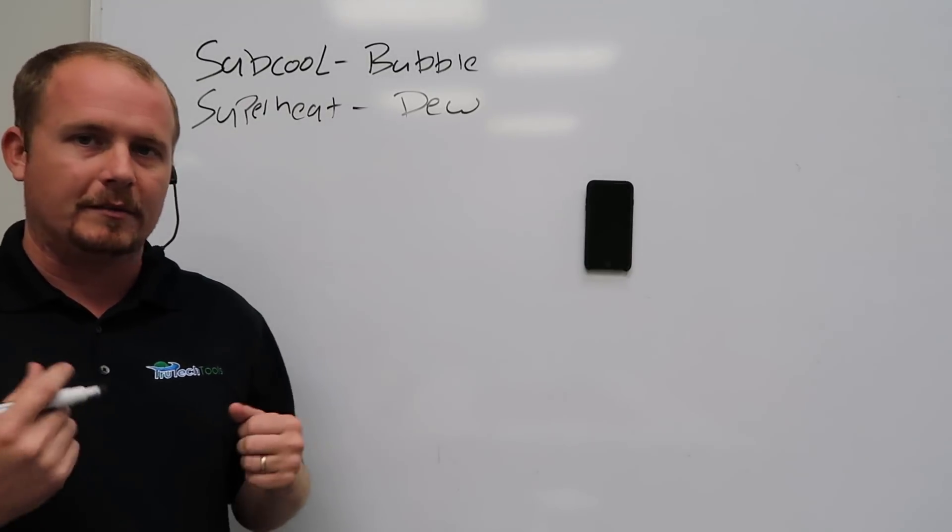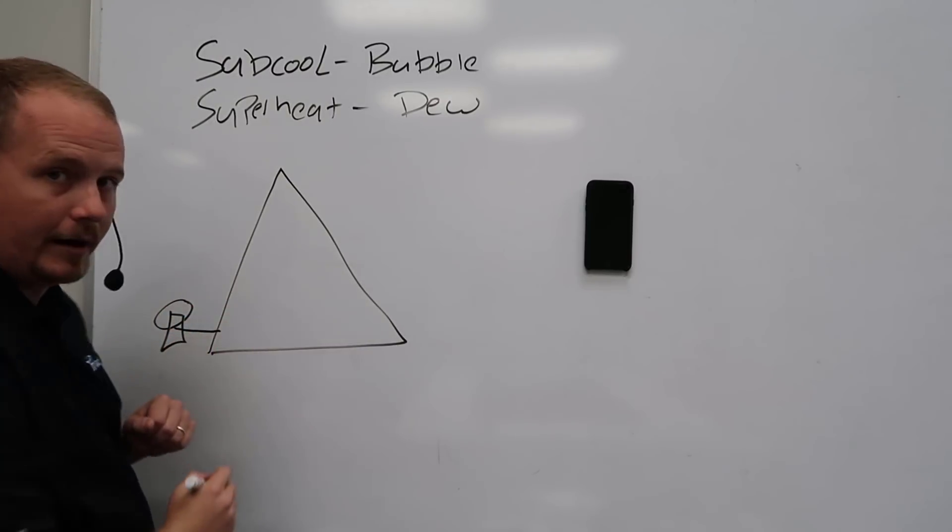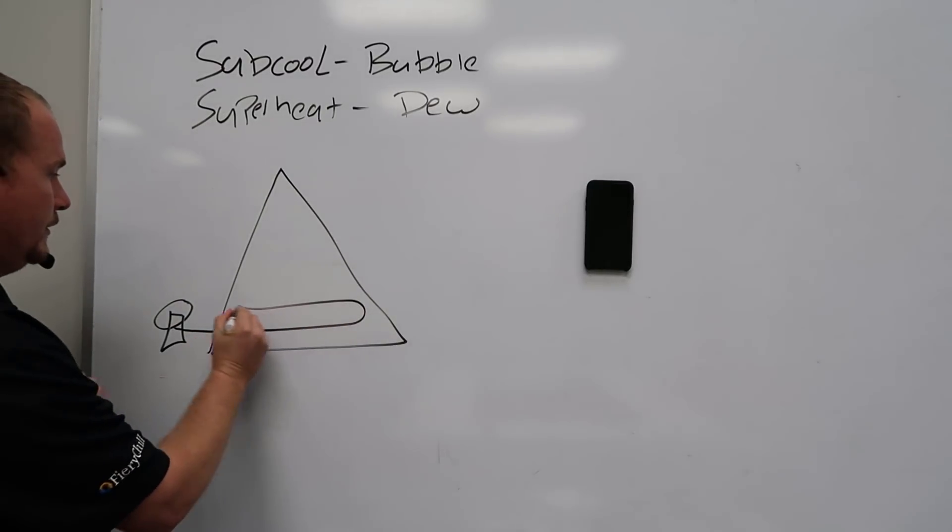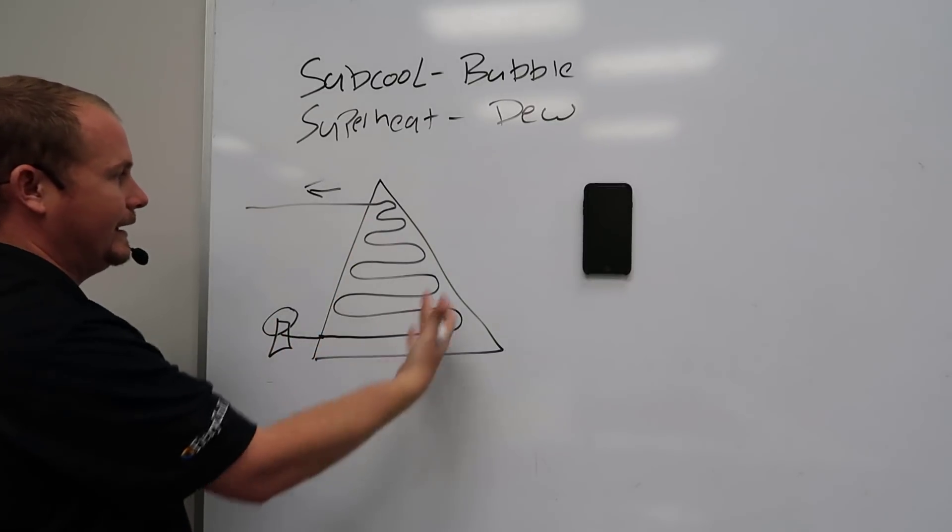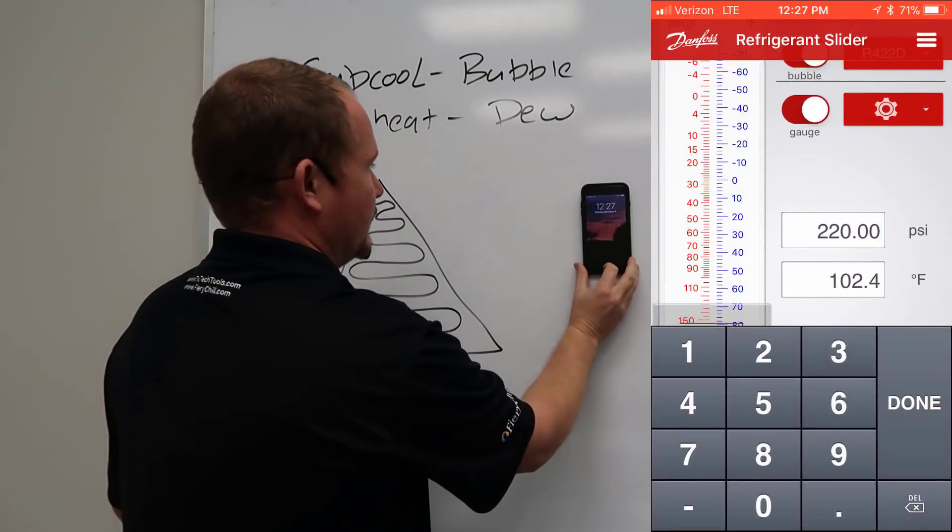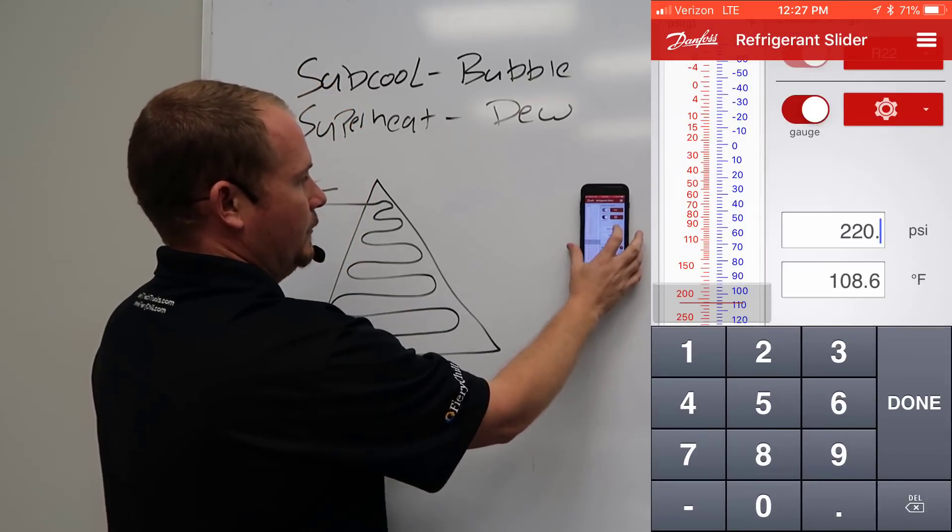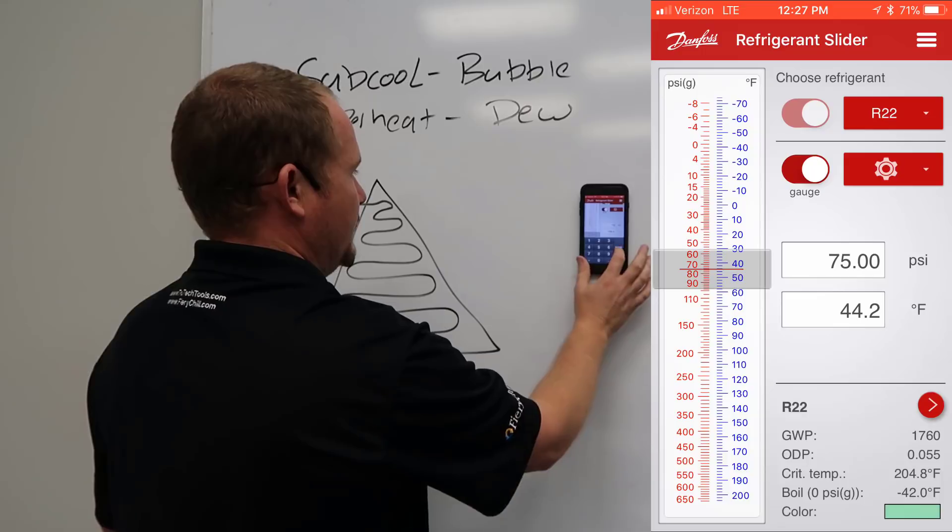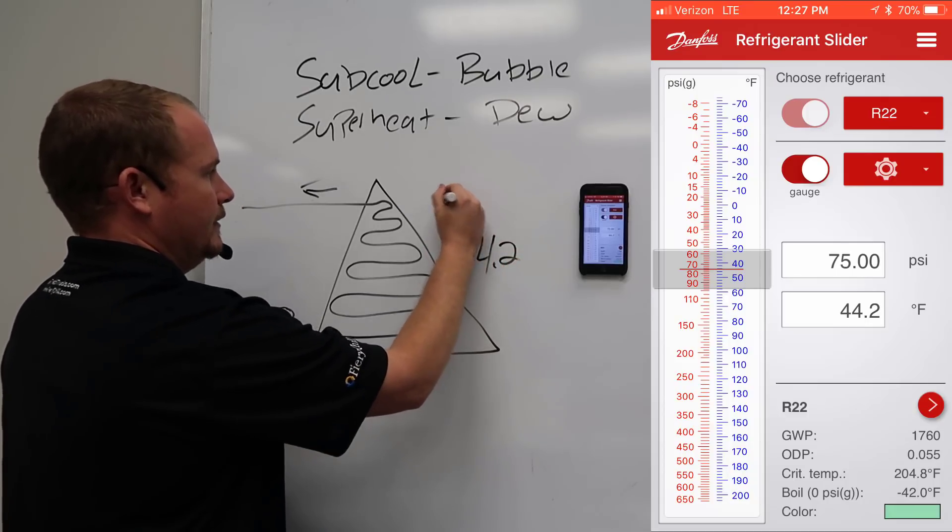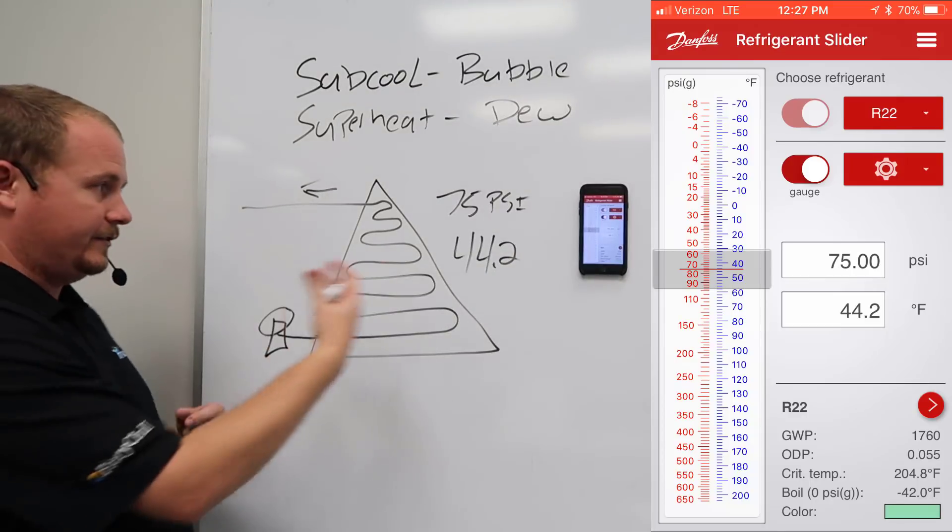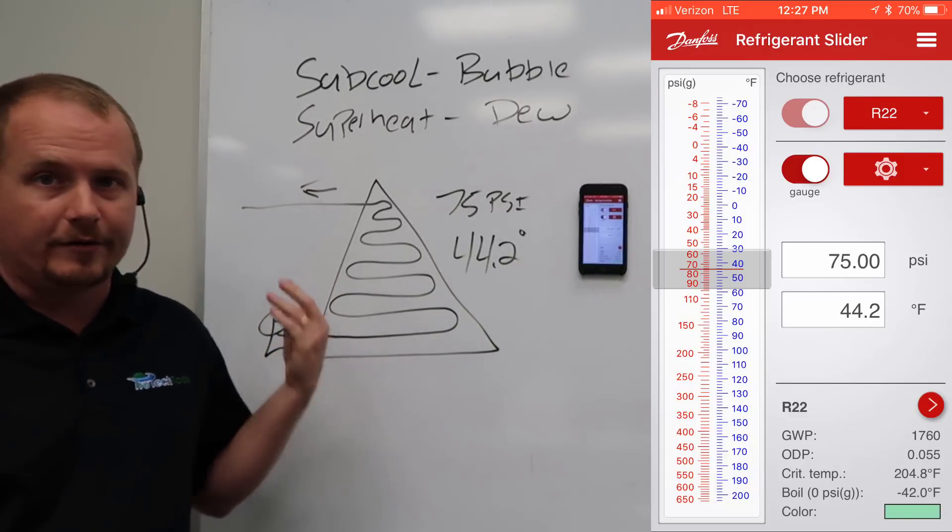But we do more things with refrigerant and readings than just superheat and subcooling. If you imagine an evaporator coil with an expansion valve feeding refrigerant into the bottom, and the refrigerant travels through, we would generally assign a temperature to this based on the saturation temperature. We would say at a given pressure it has a given temperature. Let's use the refrigerant slider app here. We'll take a traditional refrigerant like R22, and go with a typical pressure that we would see, which would be 75 psi. That's a 44.2 degree evaporator temperature. So we would say 44.2 at 75 psi, that's the temperature at which the refrigerant is boiling as it goes through that evaporator. We would call that the boiling temperature or the evaporator temperature.